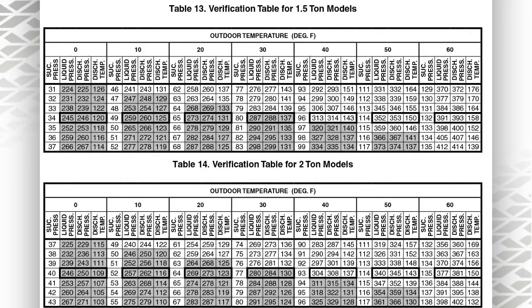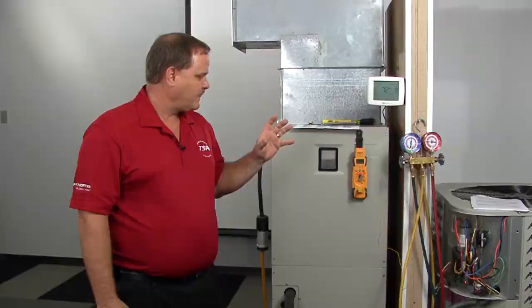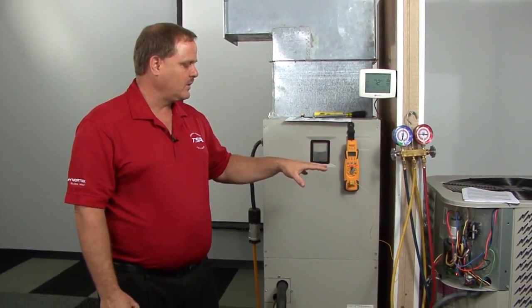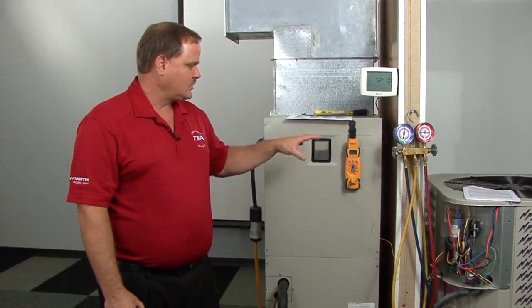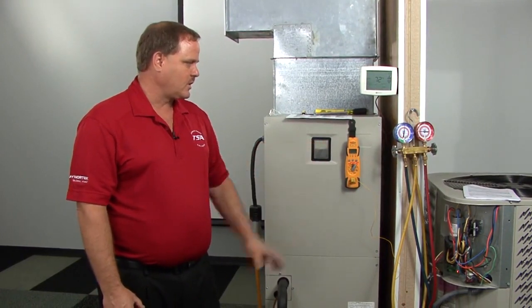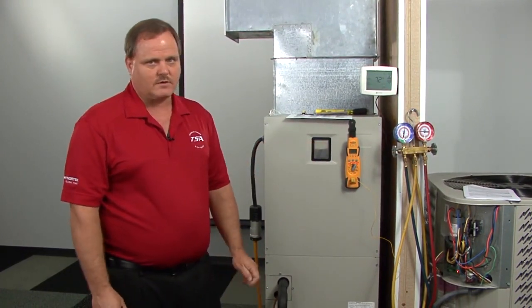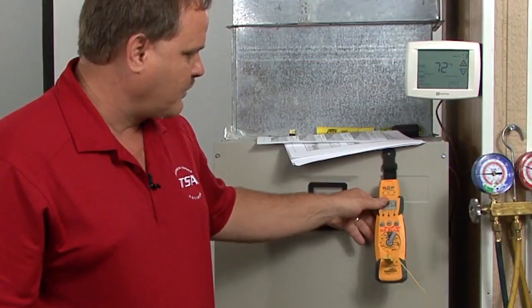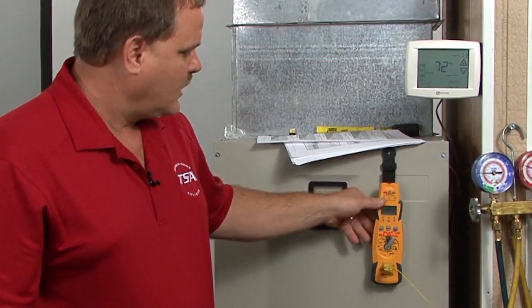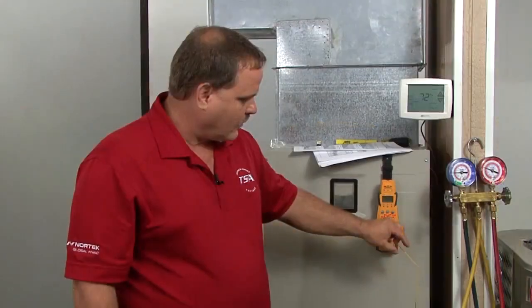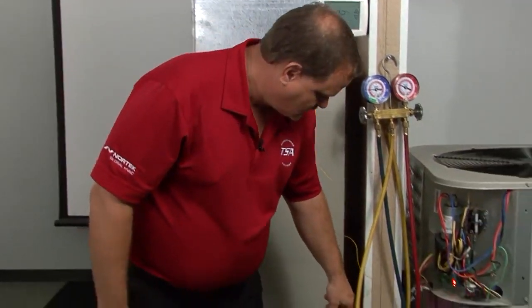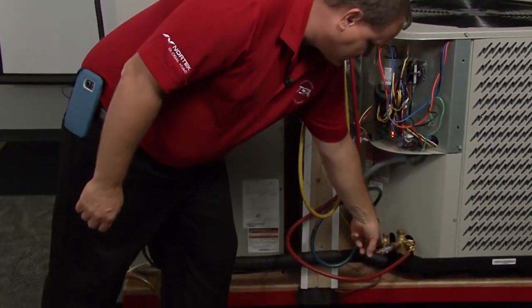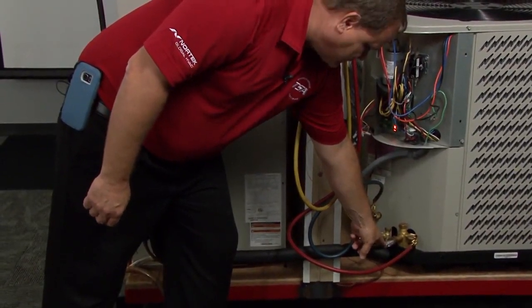One thing I am going to do here real quick is just show you this unit running in heating mode with the heat pump running and showing you that discharge temperature with the thermocouple going down to the discharge line of the unit. Okay, so I got this unit running in the heating mode, and I've got a meter hooked up here giving me the temperature with a thermocouple running down and connected to the discharge line, just like I had talked about.